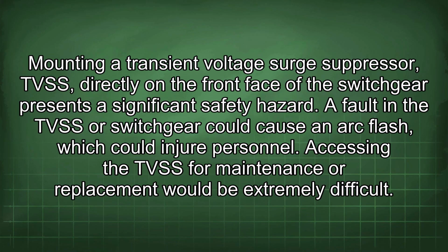Mounting a transient voltage surge suppressor (TVSS) directly on the front face of the switchgear presents a significant safety hazard. A fault in the TVSS or switchgear could cause an arc flash, which could injure personnel. Accessing the TVSS for maintenance or replacement would be extremely difficult.